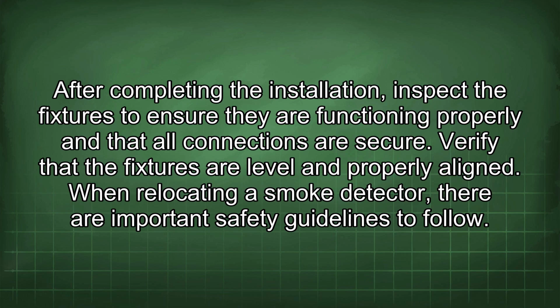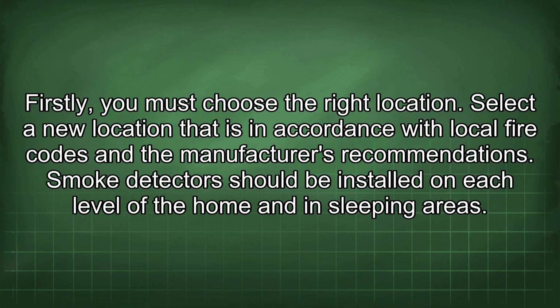When relocating a smoke detector, there are important safety guidelines to follow. Firstly, you must choose the right location. Select a new location that is in accordance with local fire codes and the manufacturer's recommendations. Smoke detectors should be installed on each level of the home and in sleeping areas.